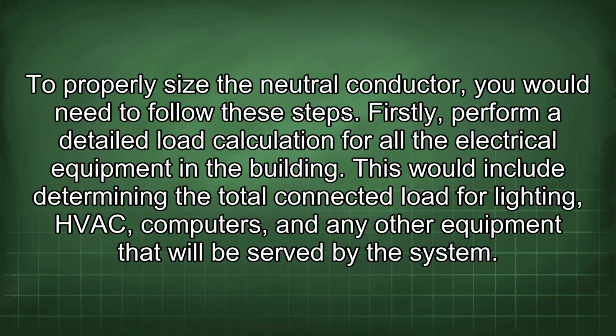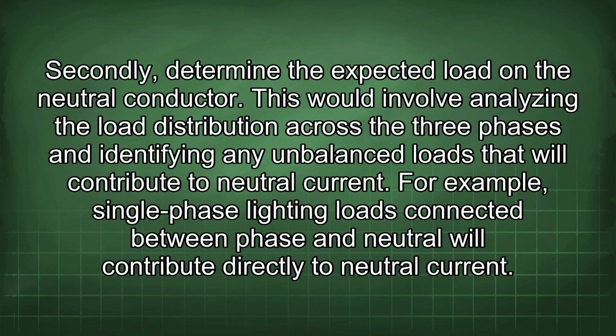Firstly, perform a detailed load calculation for all the electrical equipment in the building. This would include determining the total connected load for lighting, HVAC, computers, and any other equipment that will be served by the system. Secondly, determine the expected load on the neutral conductor. This would involve analyzing the load distribution across the 3 phases and identifying any unbalanced loads that will contribute to neutral current. For example, single-phase lighting loads connected between phase and neutral will contribute directly to neutral current.